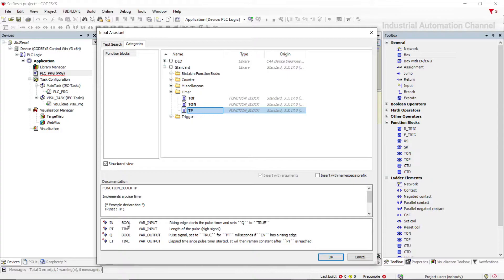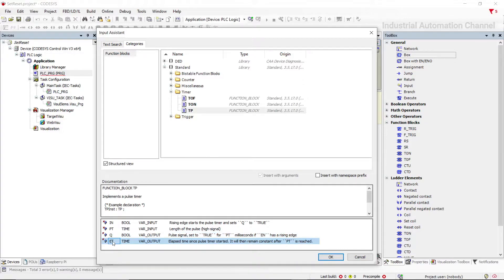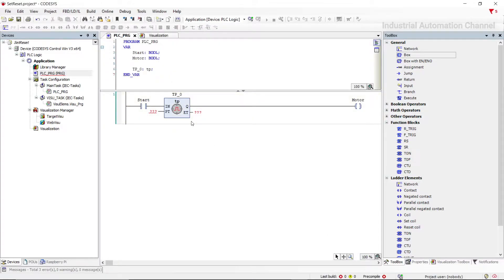We have one input with data type boolean as the actuating pulse. We need to determine the preset time, which takes a time data type. We will also have two outputs: pulse output and elapsed time. For the pulse timer, we need to determine the preset time — we want the motor to be turned off after 10 seconds, so we write 'T#10S'.